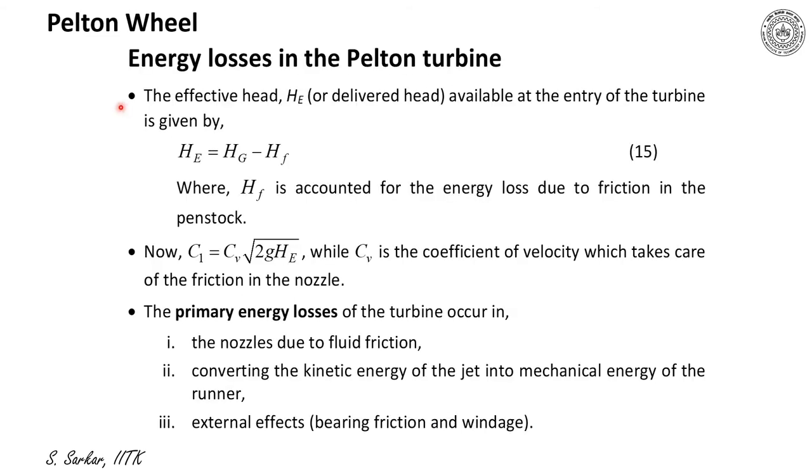Hence, the effective head H available at the entry of the turbine is given by H is equal to Hg minus Hf, where Hf is accounted for the energy loss due to friction in the penstock. Now, C1 is expressed as Cv into root over 2g into H, where Cv is the coefficient of velocity, which takes care of the effect of friction in the nozzle.